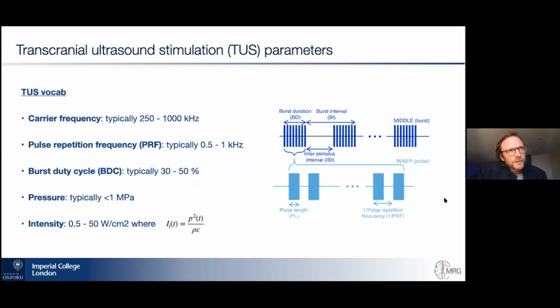It's important to understand the way in which acoustic energy is typically delivered in a TUS experiment and some of the terminology used. So I'll just cover some of that here. The ultrasound carrier or base frequency is typically between 250 and 1000 kilohertz and is delivered in a short pulse, which lasts normally about 0.5 milliseconds. Higher carrier frequencies have greater spatial resolution within the head, but they also have greater attenuation and distortion by the skull. Pulses are delivered in a train at a pulse repetition frequency of about 0.5 to 1 kilohertz.